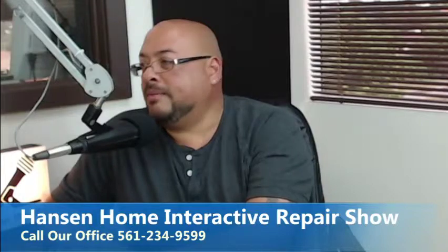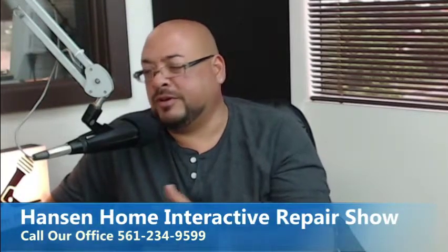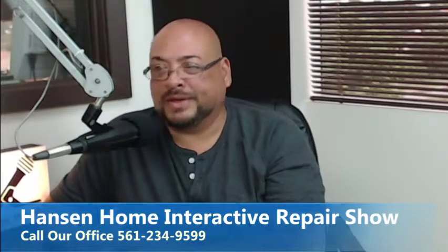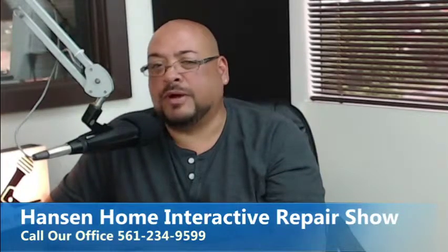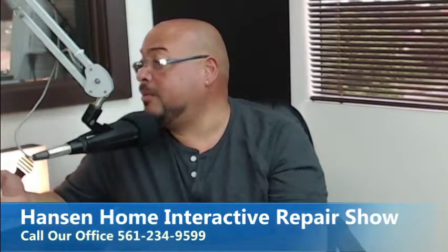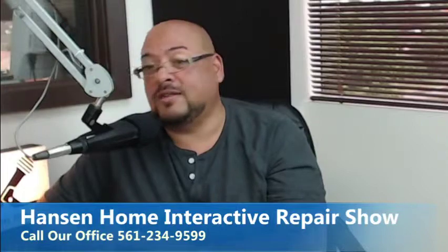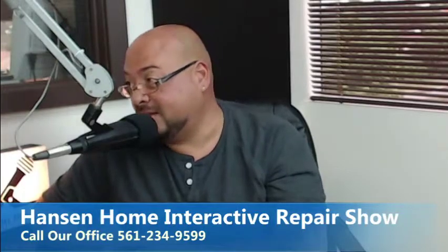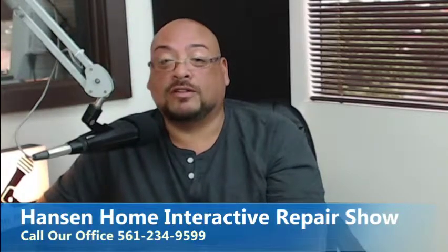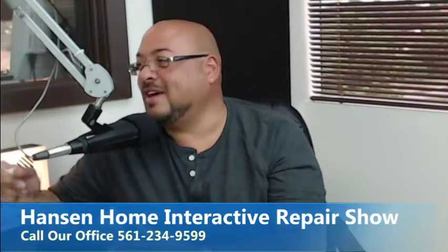Here's the thing. A lot of times up north, anyone that's been up north is going to recognize this, that lives in a building or a home where they're renting a floor. In the wintertime, our most popular call is, hey, the guy upstairs is dying of heat and the person downstairs is freezing to death. So I'd go and look to see where the thermostat was, and where was it always? Downstairs.